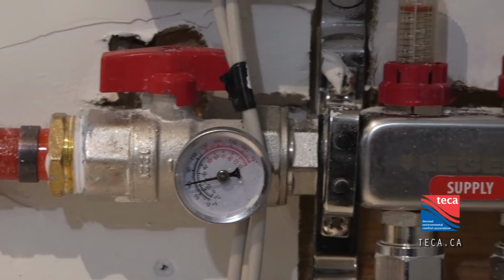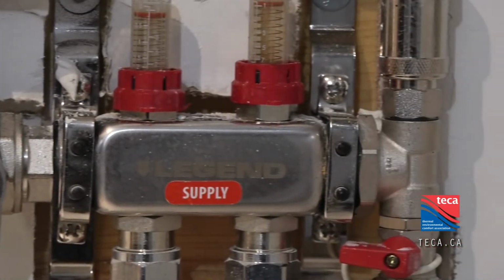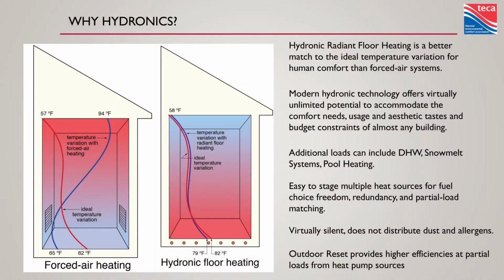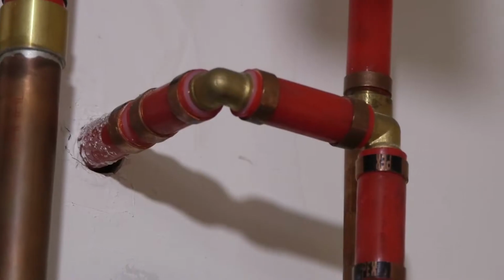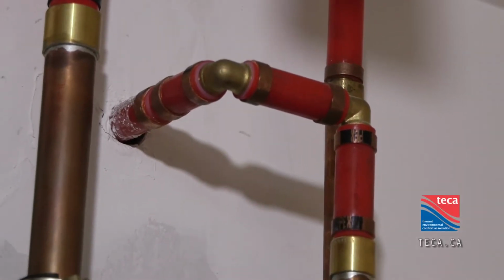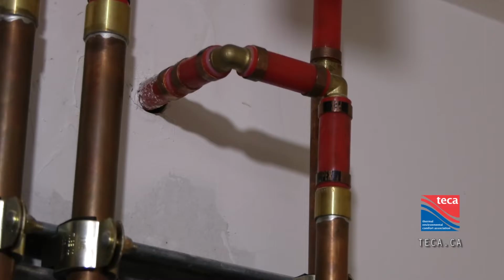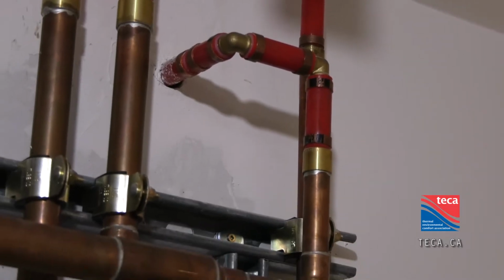Why do we use hydronics? Distribution efficiency, ultimately. When it comes down to it, we can move more heat with water than we can air, and we can move that heat further and more efficiently in smaller spaces. So builders love it. Less bulkheads, smaller pipes delivering the same amount of heat as large ducts. Again, hydronic radiant floor heating is the predominant way we heat here with hydronics. It's a great match to air-to-water heat pumps.